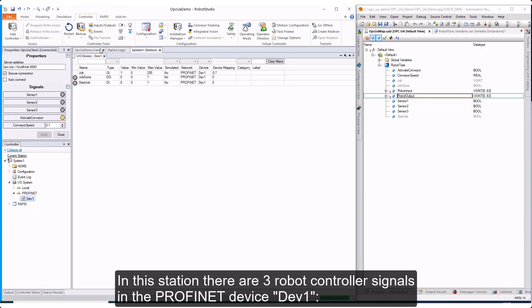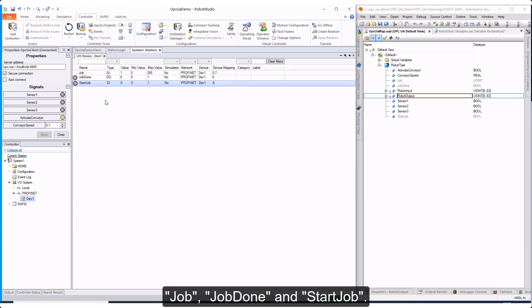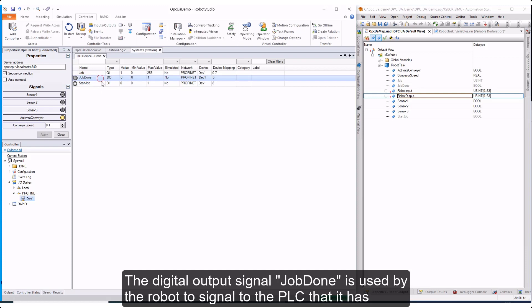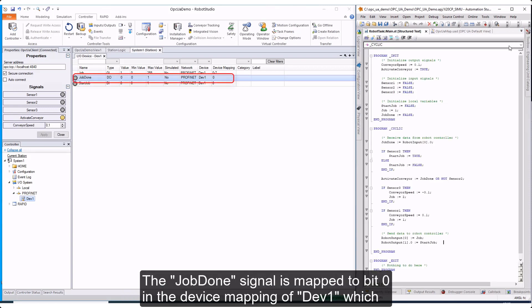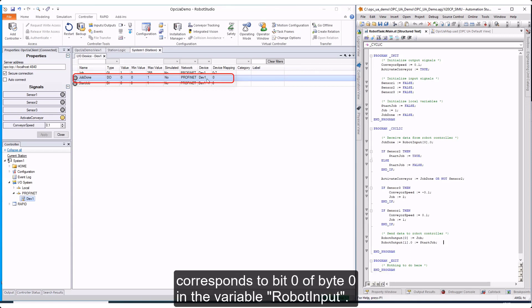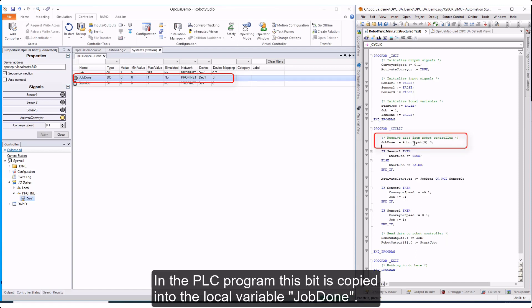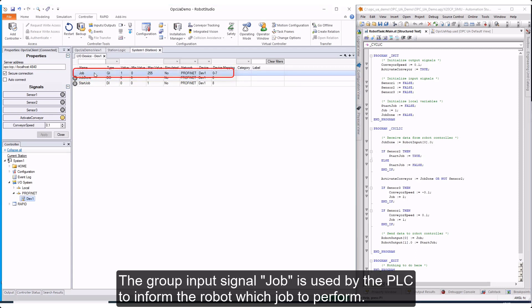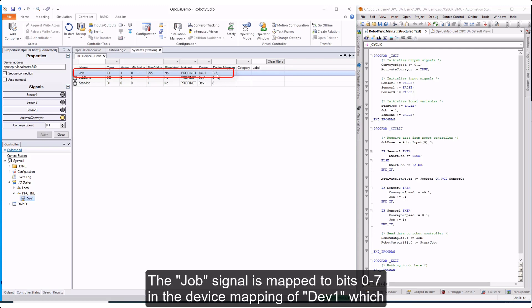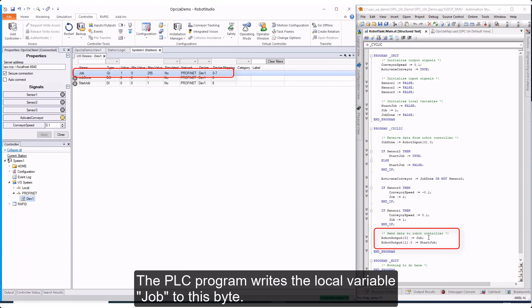In this station, there are three robot controller signals in the PROFINET device DEV1: Job, Job Done, and Start Job. The digital output signal Job Done is used by the robot to signal to the PLC that it has finished performing a job. The Job Done signal is mapped to bit 0 in the device mapping of DEV1, which corresponds to bit 0 of byte 0 in the variable robot input — in the PLC program, this bit is copied into the local variable job done. The group input signal Job is used by the PLC to inform the robot which job to perform; it is mapped to bits 0 to 7 in the device mapping of DEV1, corresponding to byte 0 in the variable robot output, and the PLC program writes the local variable job to this byte.